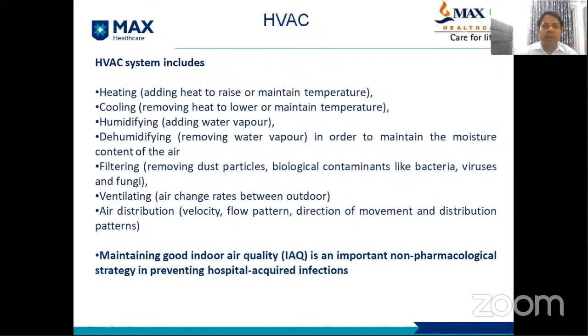So what do we mean by HVAC systems? Heating, the addition of heat to raise or maintain temperature; cooling, removing heat to lower or maintain temperature; humidifying, adding water vapor; dehumidifying, removing water vapor in order to maintain the moisture content of the air; filtering, removing dust particles and biological contamination like bacteria, viruses, and fungi; ventilating, air change rates between outdoors and indoors; and air distribution, that is the velocity, flow pattern, direction of movement, and distribution patterns. Maintaining good air quality is an important non-pharmacological strategy in preventing hospital-acquired infections.